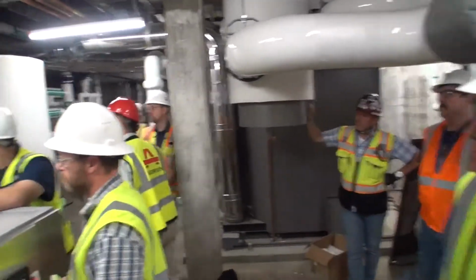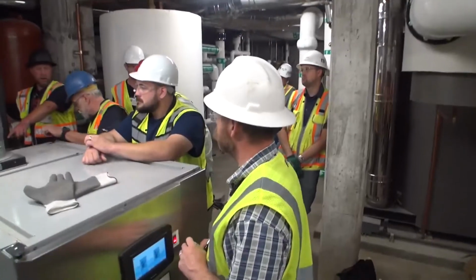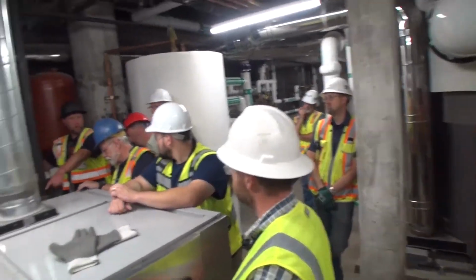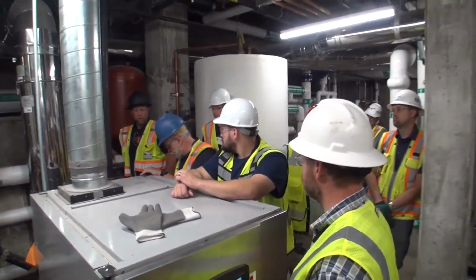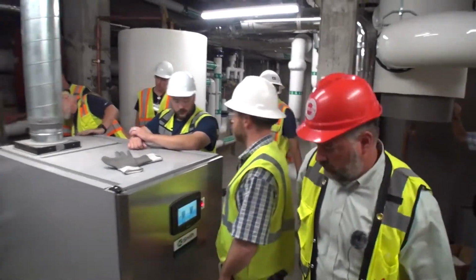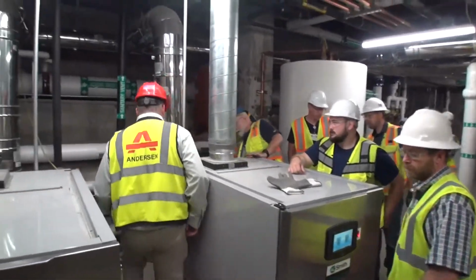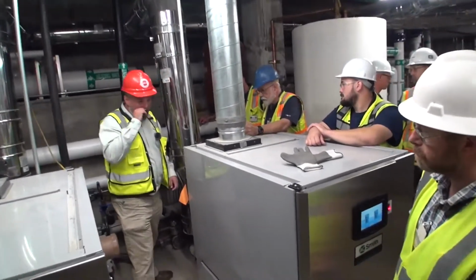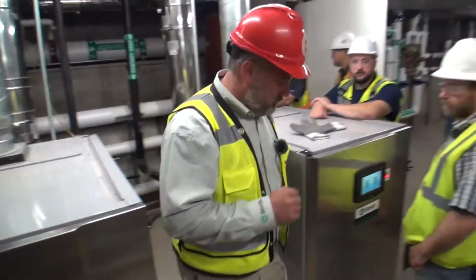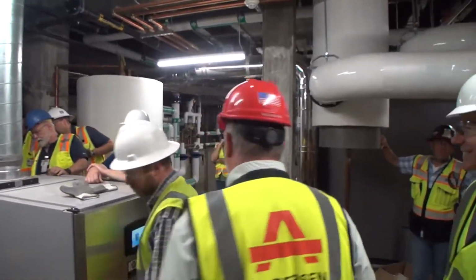Are you able to lock out, tag out on that shutoff, the disconnect? What now? Sorry? Are you able to lock out, tag out off this disconnect for the boiler power? Should be. Yeah, yes you are. Yep. You are listed as a Yes, yes.